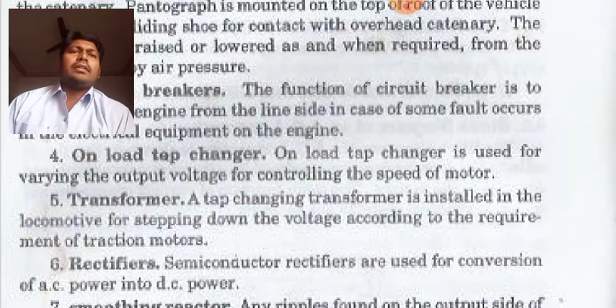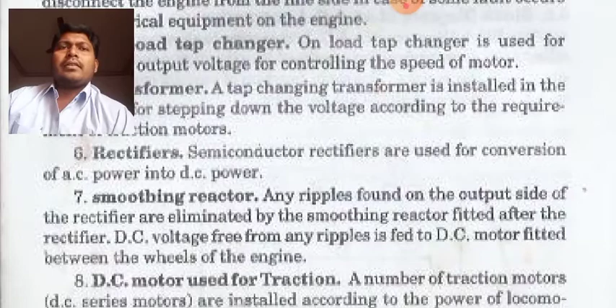Because we are using DC motors for running the locomotive. Now as the motor is DC, the supply given to this motor should also be DC. So we require a rectifying unit. The rectifiers used here are semiconductor rectifiers, which are used for the conversion of AC power to DC power. Smoothing reactors. Any ripples found on the output side of the rectifier are eliminated by the smoothing reactor fitted after the rectifier.